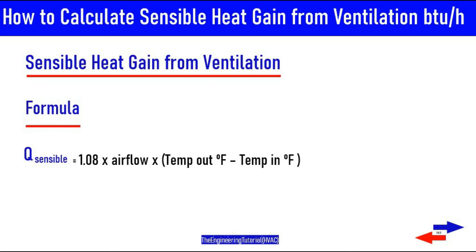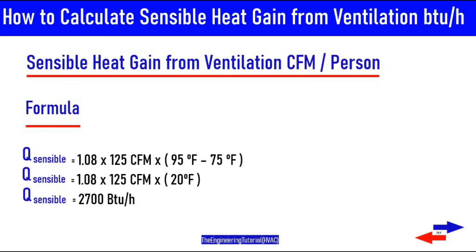For the first example, using the CFM per person method: Q equals 1.08 times 125 CFM times (95°F minus 75°F), which gives us 2,700 BTUs per hour. So 2,700 BTUs per hour is the amount of heat gain from ventilation that must be cooled and dehumidified before it can be delivered to the space.